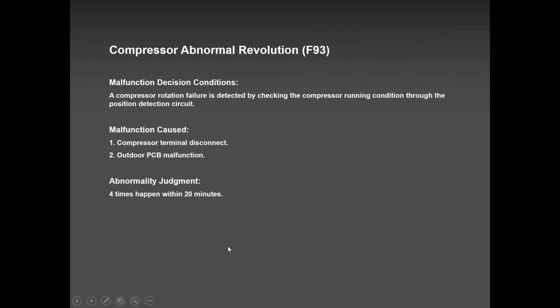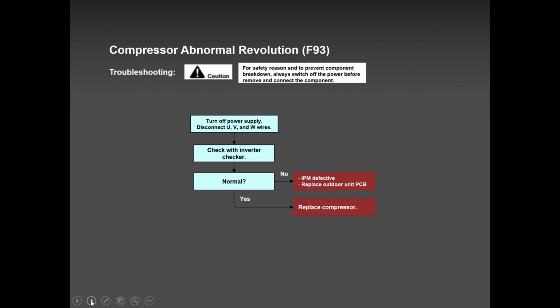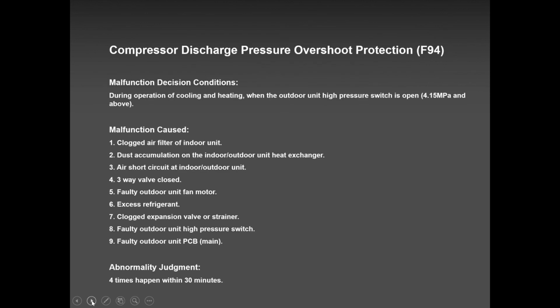F93 is not a good code. It's a bad code, and I say bad meaning compressor. So with F93, I may have got 1 or 2, and that's about it. I never got an F93 since then. So I'm talking about 6 years now with Panasonic, and I can think of 2 calls only on F93. And I hate this code because it's a big job, compressor replacement and all that kind of thing. And especially when you're replacing a compressor on a -15 or -5 day, your brain is also frozen, you know.